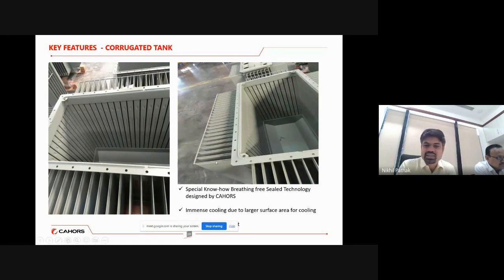These corrugated fins are designed in such a way that they facilitate the expansion and contraction of the oil by opening and bulging, and they will also come to a standstill once the temperature goes down and the load on the transformer goes down.